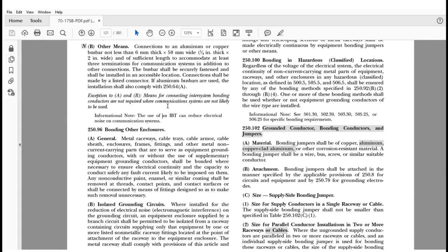All right. Again, I want to remind you, you are still prohibited from terminating CSST, photovoltaic, any of those other types of systems that are not communication systems to the inter-system bonding termination device. You have to use the other means and put in a bus bar and follow these directions if you want to bring it all in one. Doesn't mean you have to have both. If you only have communication, you can do the one device. If you want to have everything come to one location, then you've got to do the other means.